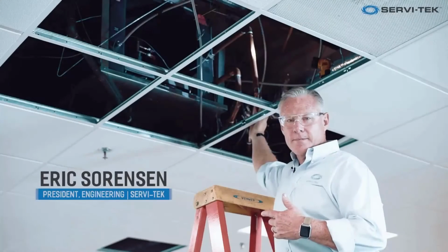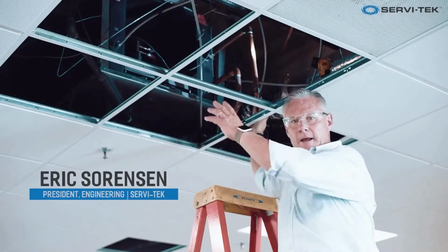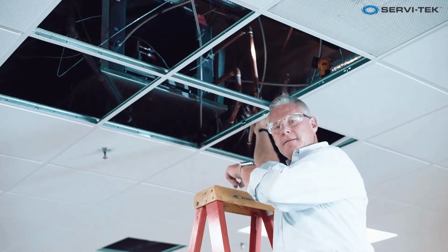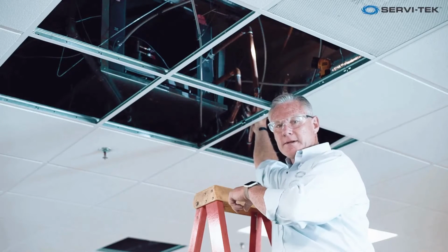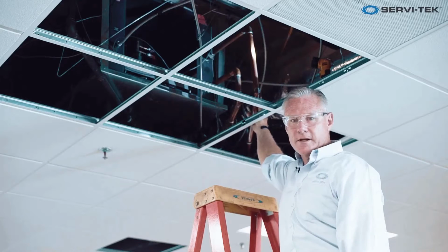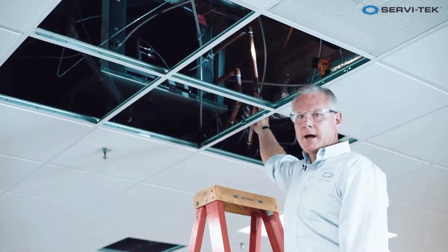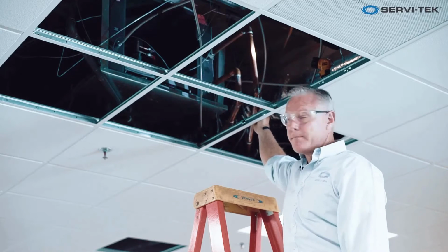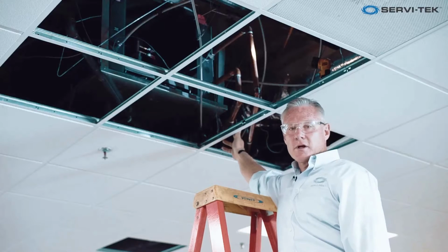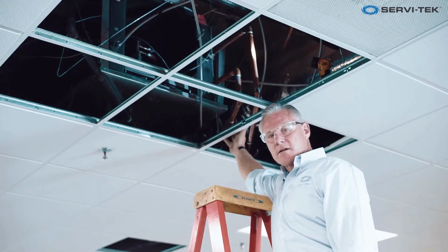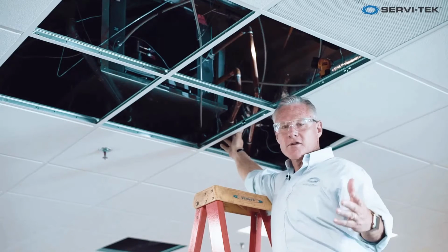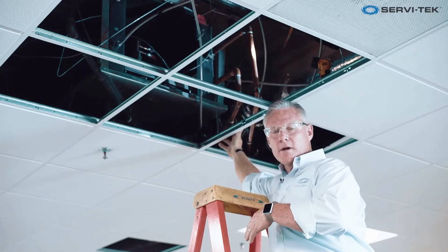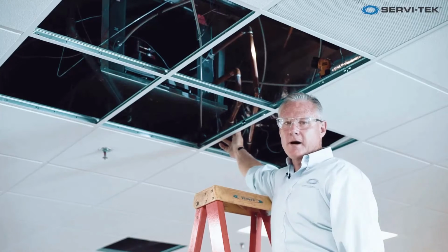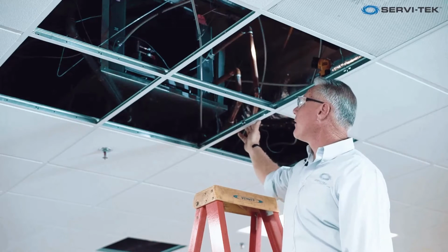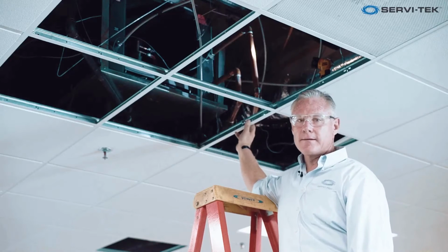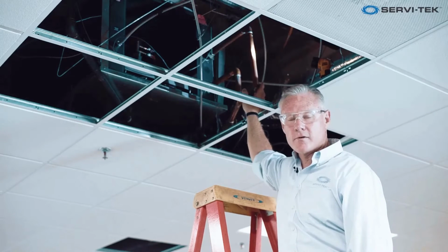Maintenance on the water source heat pump system is relatively simple, as long as you have access. The unit has filters built into it that get changed out, usually box pleated filters, pretty straightforward. Cleaning the coil is important, but one of the more important things to do is clean the strainer. If the strainer gets clogged up, the flow starts to stop. When the flow starts to stop, the unit tends to overheat and can trip off on what's called high head pressure. So again, relatively simple unit, not a lot to do on the refrigeration circuit side.